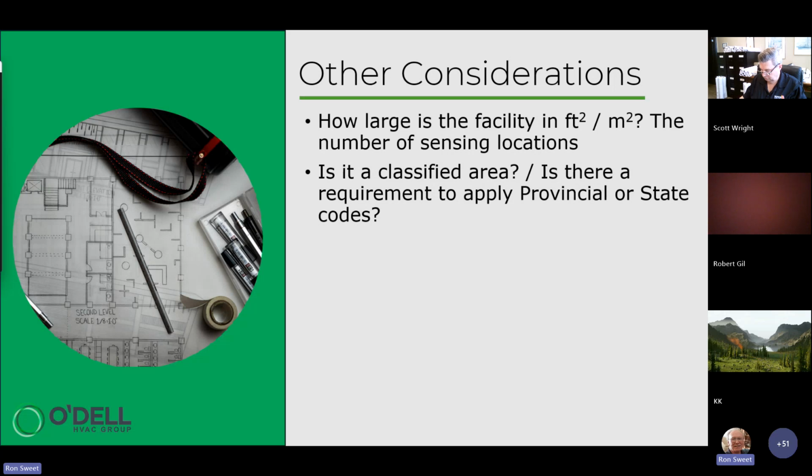An intrinsically safe device gets that classification by way of the fact that it was designed as a very low current device. There is not enough current and enough voltage flowing through the electronics within that device to create a spark should any component or a battery be separated from the electronics. So there's no source of ignition.